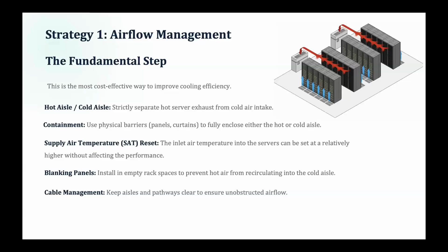So with the increase in energy prices and increasing awareness about energy efficiency, the supply temperature started to increase, because the electronics inside the servers can take a raised server supply temperature, which did not make the server's performance degrade in any way. So it was basically a mindset change or a behavioral change, and it has a very huge impact on the energy aspects of cooling, because a 1 degree increase in supply air temperature will increase the cooling efficiency by approximately 4 to 5%. So any raise in supply air temperature without affecting the server performance is a huge energy efficiency gain.